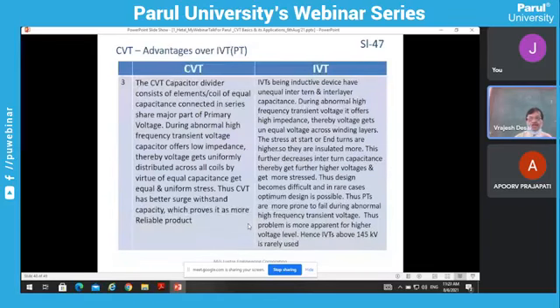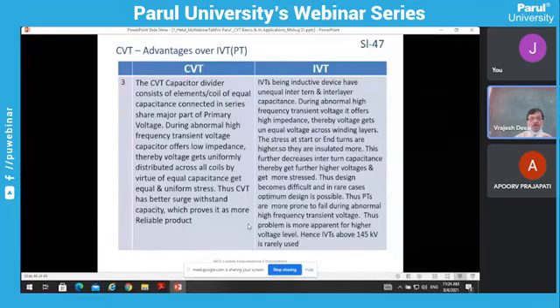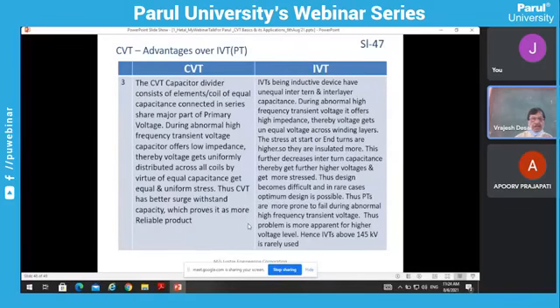The biggest advantage of the CVT is that all the capacitor coils have equal capacitance and are connected in series. So whenever a transient voltage like a switching surge or lightning impulse comes, it offers very low impedance, since Xc is equal to 1 upon 2 pi f c. So the voltage is uniformly distributed across all the coils, because all the coils have equal capacitance. It will share the voltage. That means the CVT is a more capable and reliable product in case of high voltage surges.